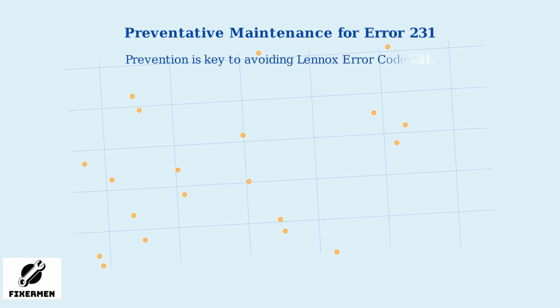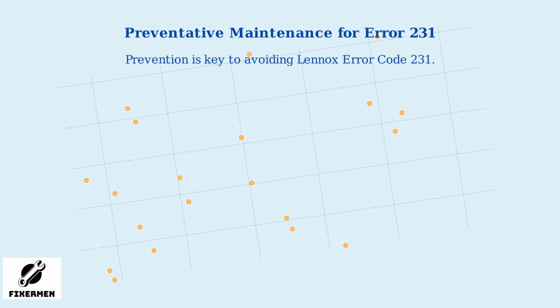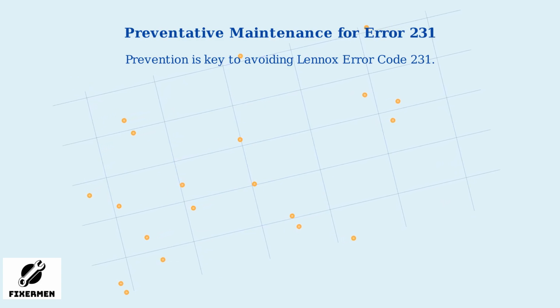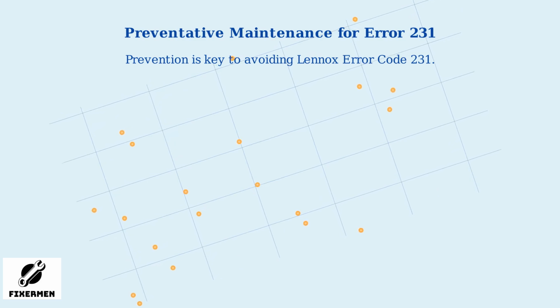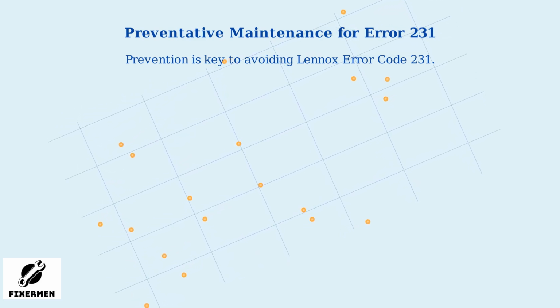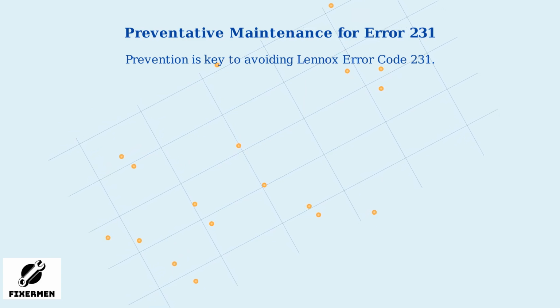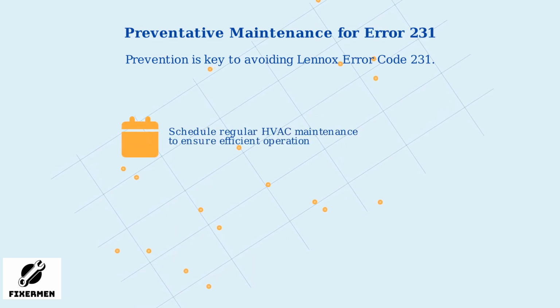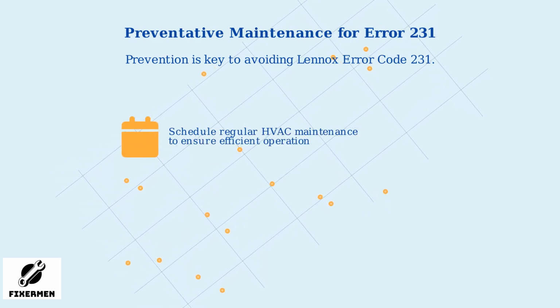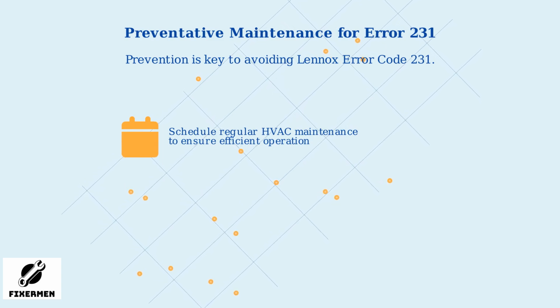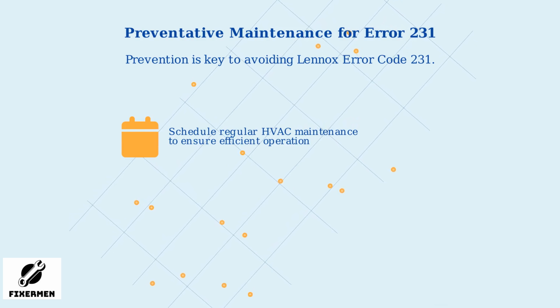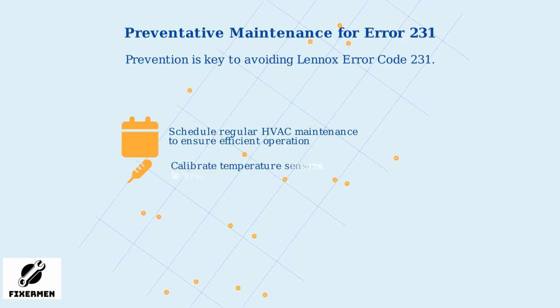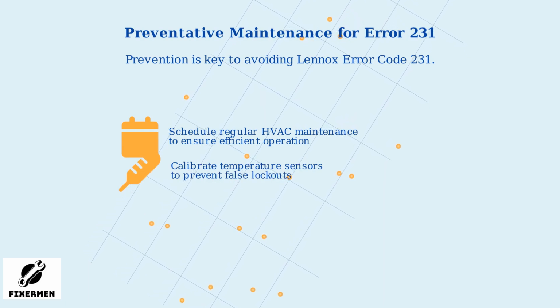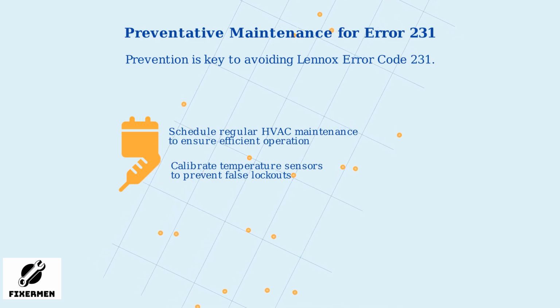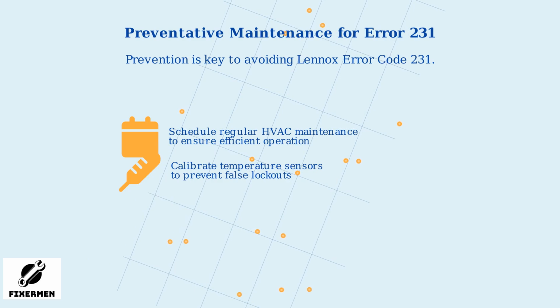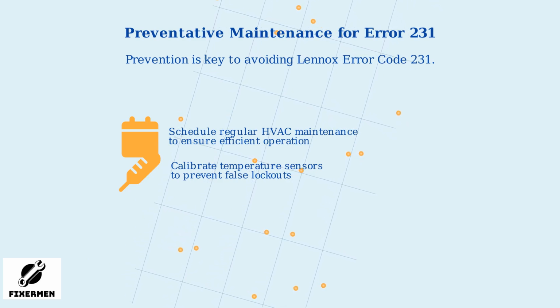Prevention is key to avoiding Lennox Error Code 231, the low ambient lockout condition. By implementing regular maintenance practices, you can significantly reduce the chances of this error occurring and ensure your HVAC system operates efficiently throughout the year. Schedule regular HVAC maintenance to ensure your system is operating efficiently. Professional technicians can inspect components, update firmware, and catch potential issues before they trigger lockouts. This includes calibrating temperature sensors, which are critical for detecting ambient conditions accurately. Miscalibrated sensors can cause false lockouts, so regular calibration prevents unnecessary shutdowns.